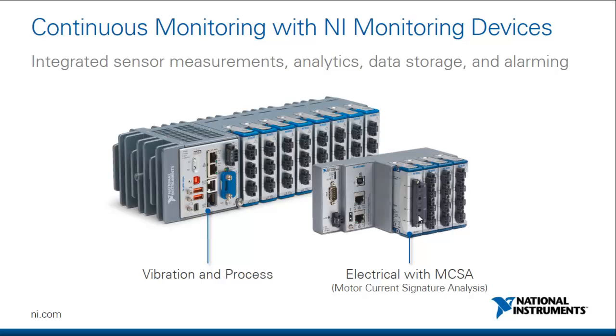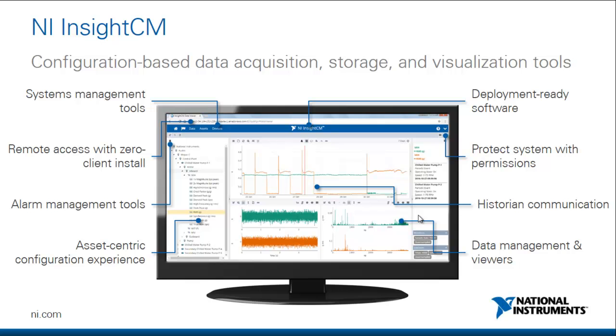The NI monitoring devices, which you can see on the screen here, have been designed to do the sensor data acquisition, the raw time waveform data analytics, data storage, as well as the alarming capabilities. NI has designed a few different systems that have IO specific to different types of assets — everything from vibration and process type measurements, to being able to monitor three-phase AC induction electric motors with motor current signature analysis. These devices then communicate to the Insight CM server software, which we can see on the screen here. This server-based software gives us the ability to configure our systems, to be able to store this data, and ultimately, to be able to visualize it.